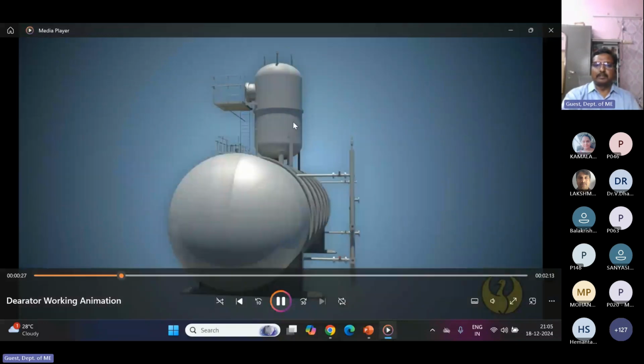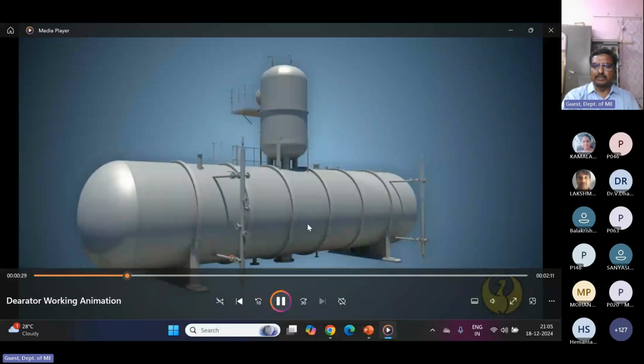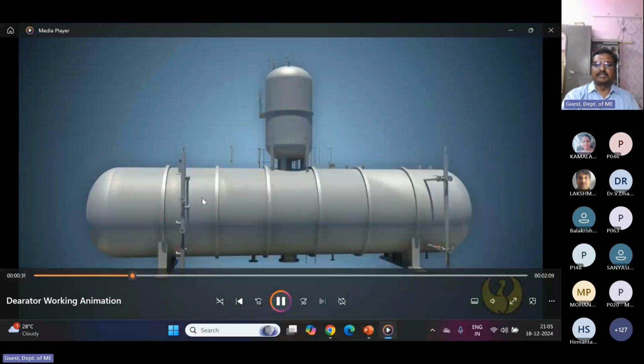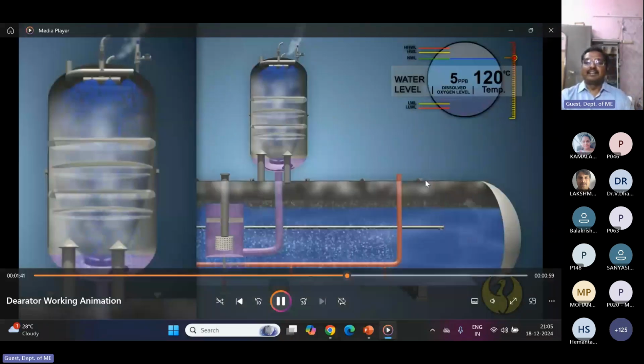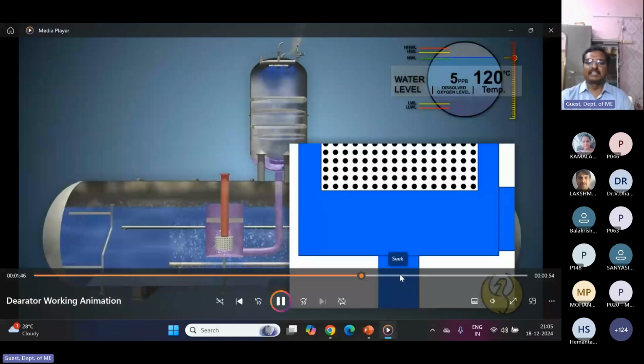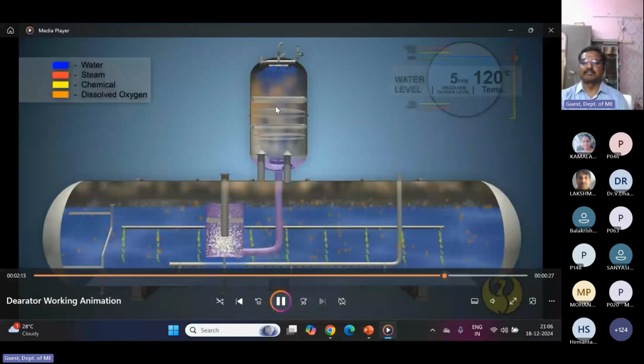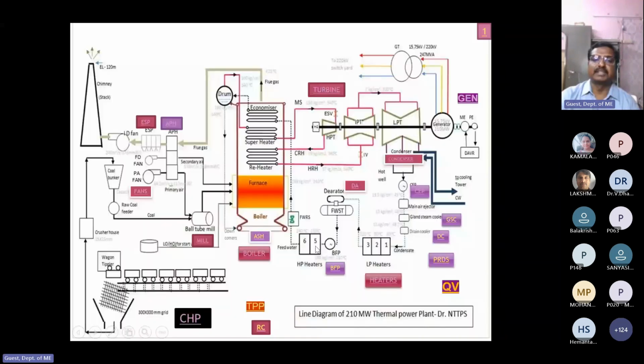Actually, this top part is the deaerator and it is a storage tank. It is called the feed water storage tank. This is the method of feed water heating in the deaerator and removing the gases. After the deaerator, the water goes through the HP heaters and goes to the boiler again. So this is the overall stuff.